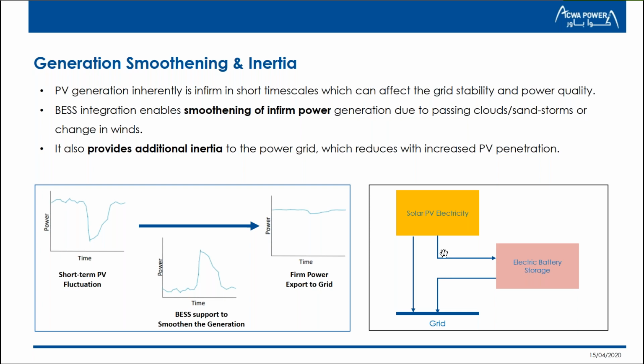Now, once BESS is integrated along with the PV, it can help smoothen these short duration, sharp fluctuations in PV, which is depicted pictorially in the left-hand side graph here. So let's say if there is a sharp drop in PV, BESS can complement that, and from the grid interface point of view, it's a relatively smoother curve. Right, and it does not mean that we need to have two separate BESS systems for the ramp rate management and smoothing. It can be the same asset with certain allocation of energy for both the use cases, and both can be done with the same asset and optimization can be achieved.